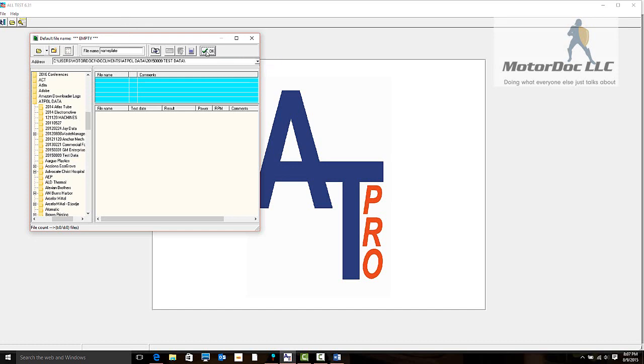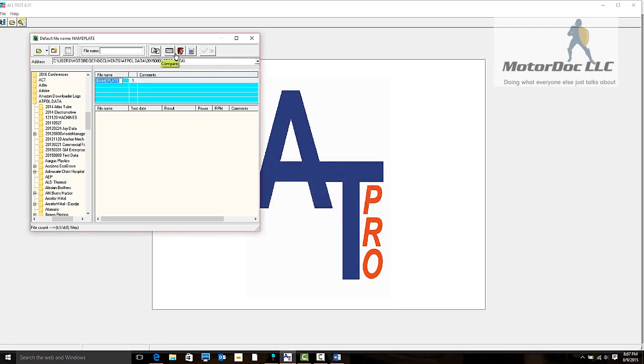When we highlight this, the header file has popped up. It is an induction motor, three phases, acquired three phases, analyzed current and voltage. The machine is operating on a dyno, so we're just going to say no driven equipment. The power value is 30 horsepower, it is a 1765 RPM machine, 460 volts. The full load current is 34.5 amps. We know from operating that we saw it under no load at 8 amps.